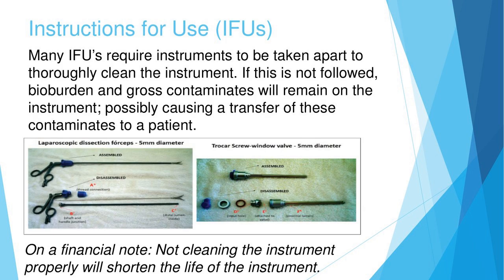Disassembly of instruments is another area of concern. Many IFUs require instruments to be taken apart to thoroughly clean the instrument. If this is not followed, bioburden and gross contaminants will remain on the instrument, possibly causing a transfer of these contaminants to a patient. We look at laparoscopic instruments as an example. They look simple to clean, but upon further inspection, there are many pieces and parts to clean. So not knowing the instruments can cause that cross-contamination we talk about. Also, on a financial note, not cleaning the instrument properly will shorten the life of the instrument in addition to putting the patient at risk.